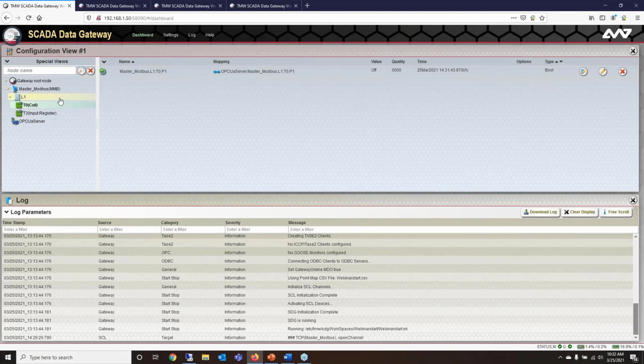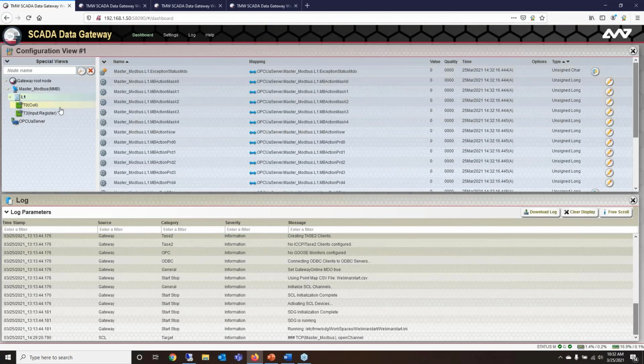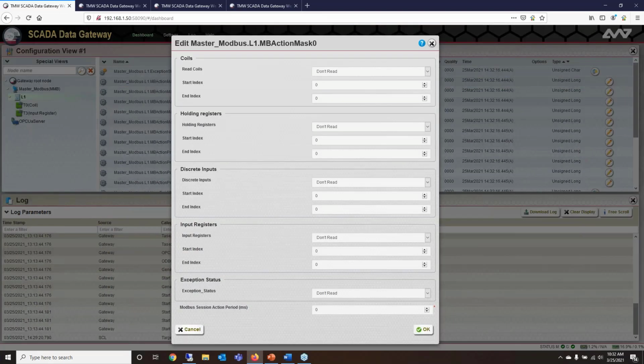So let's talk about how you can get these different data transfer types that we talked about in the previous slide. So you go back to L1, and this time I'll click on it, and we'll see all the information inside of the L1. In this situation, we have a bunch of action masks. This is essentially what is the gateway going to do. So let's just click this little pencil icon here to edit it. And you'll see a bunch of stuff filled out here. For a Modbus, you can essentially perform these reads or pulls like we were talking about before. We've got the coils, the holding registers, discrete, input registers, everything along those lines are here.